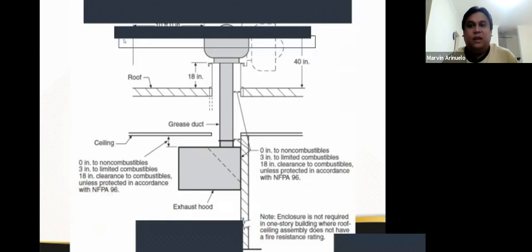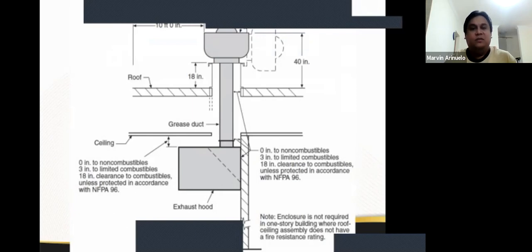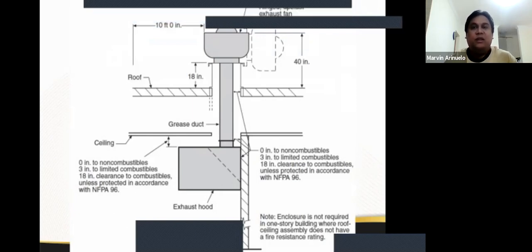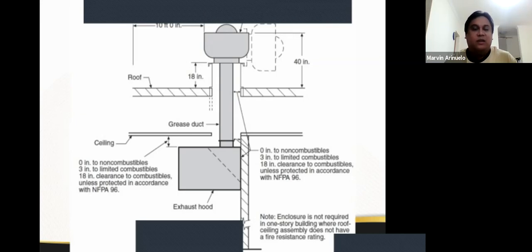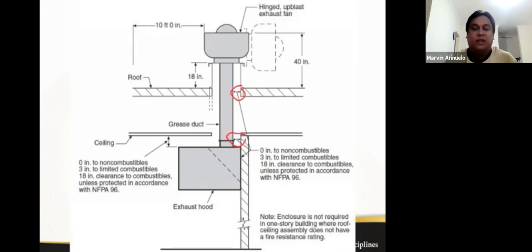So this is your typical exhaust hood connected to your exhaust fan. If you have a grease duct, this is also one of the sources of fire. It must be cleaned if there is much accumulation of grease. And you need to maintain some distance from the walls, or some clearance, unless protected according to NFPA. This is just for accessibility and maintainability as well.